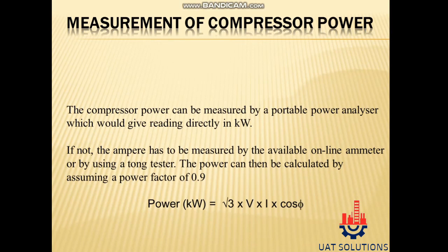Measurement of compressor power. The compressor power can be measured by a portable power analyzer, which would give a reading directly in kW. If not, the ampere has to be measured by the available online ammeter or by using a tong tester. The power can then be calculated by assuming a power factor of 0.9. Power in kW equals √3 × V × I × cos φ, where I equals current and V equals volts.